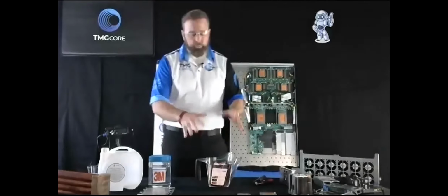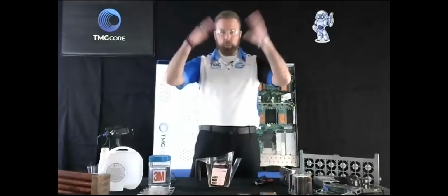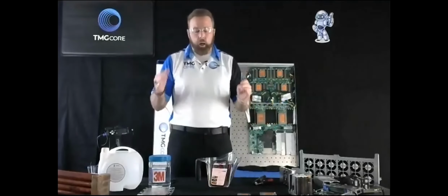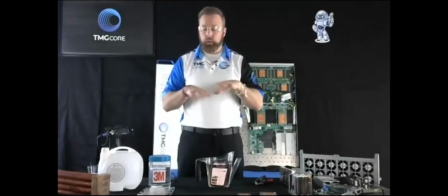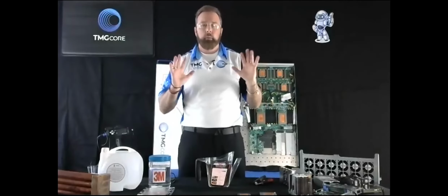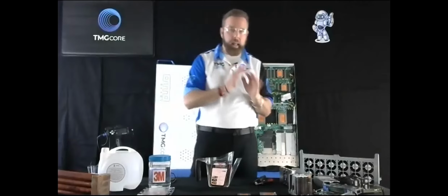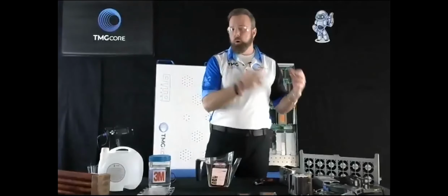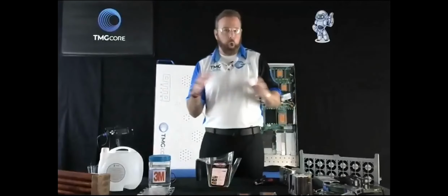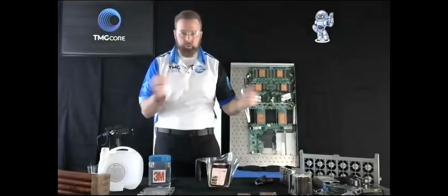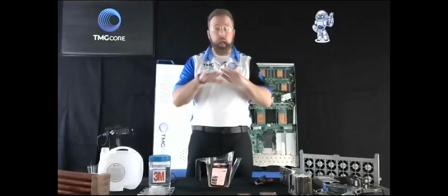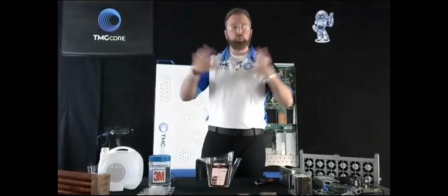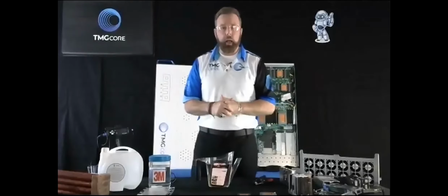One of the ways we prevent concern about fluid loss because of price is that our systems, and two-phase liquid immersion cooling in general, are not pressure vessels, they're not ASME stamped pressure or vacuum vessels. So low cost, you don't have to worry about getting all the stamps and certifications because we run at atmospheric pressure, and we control the entire system at atmospheric.